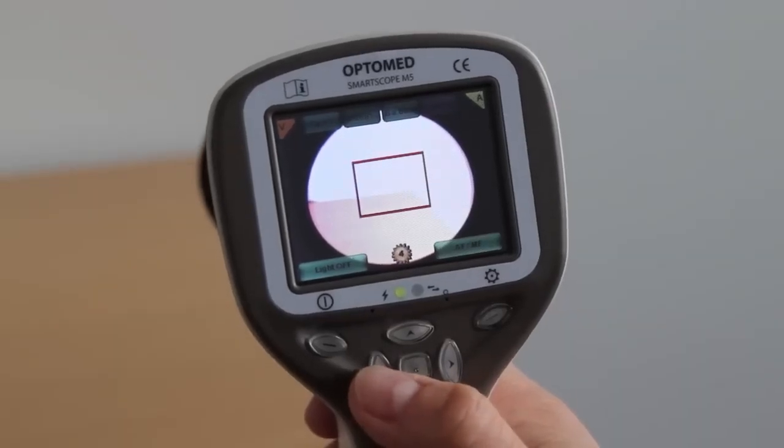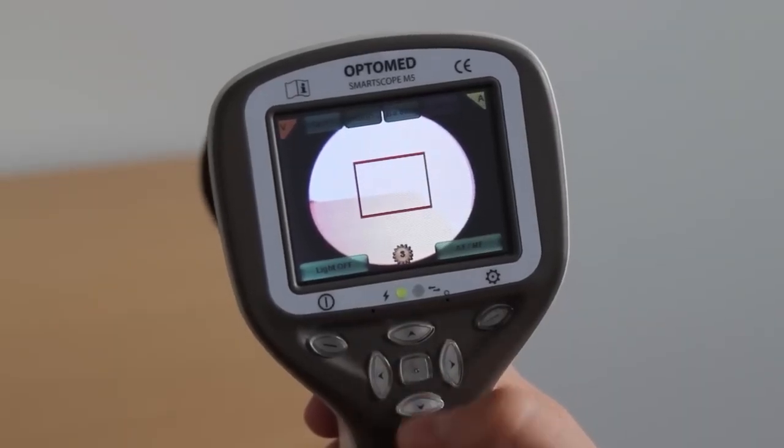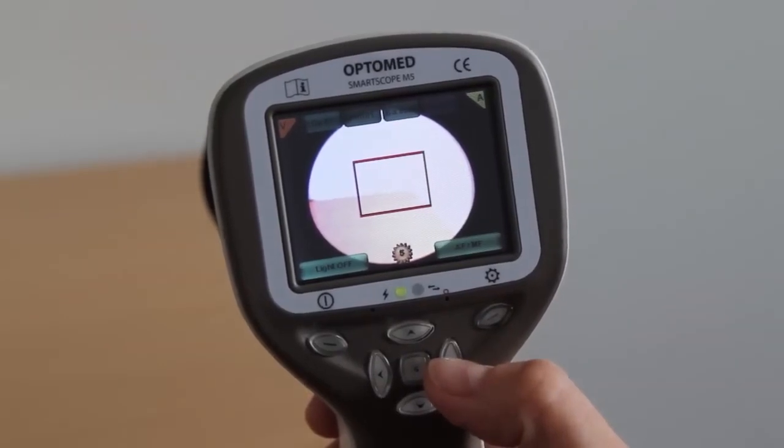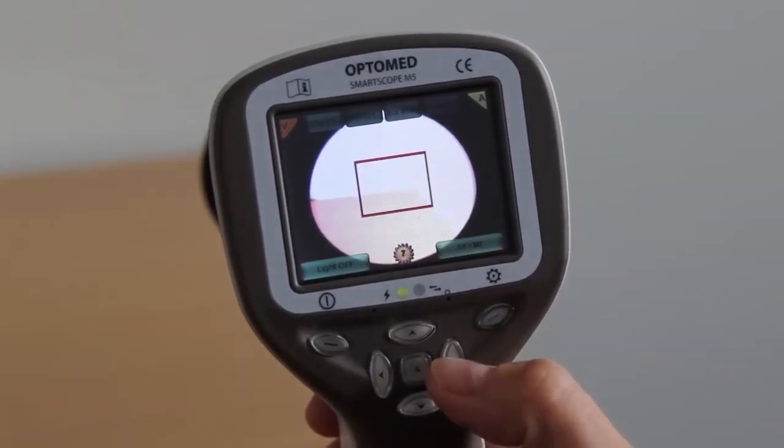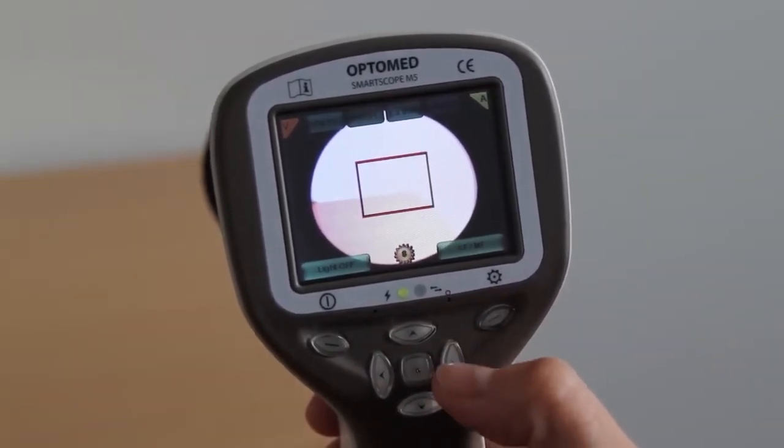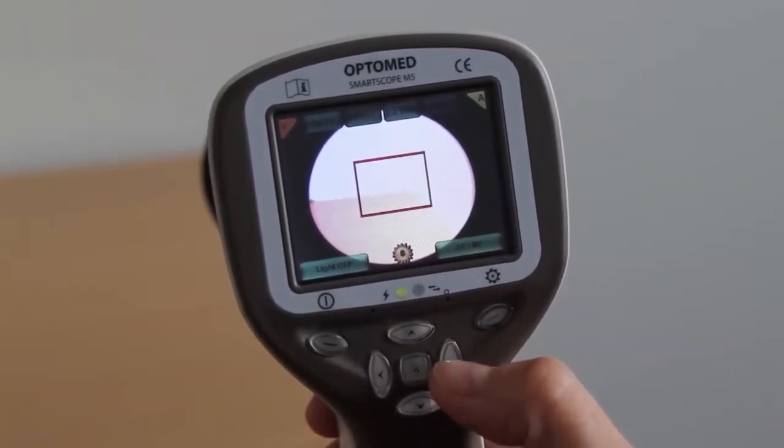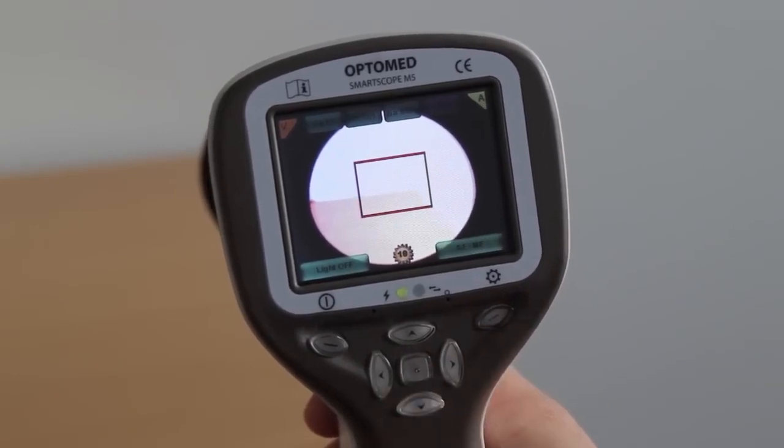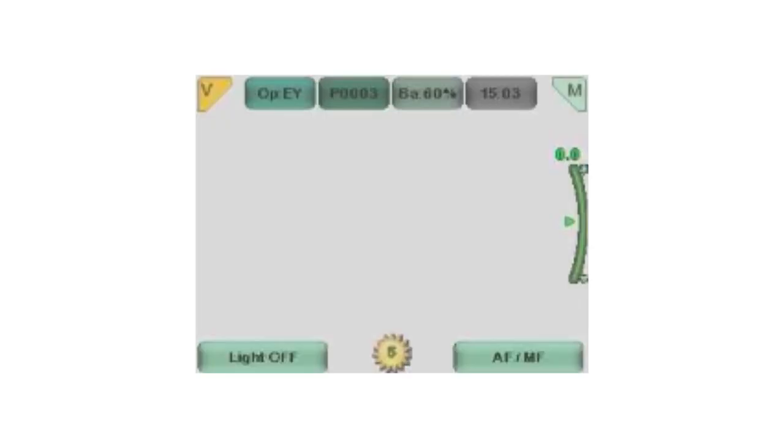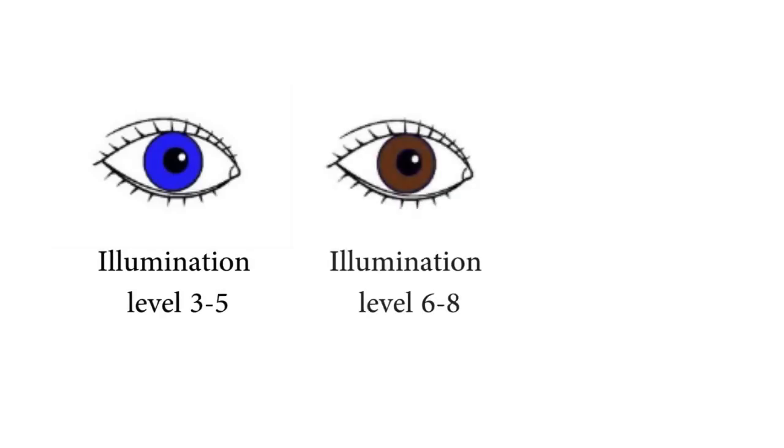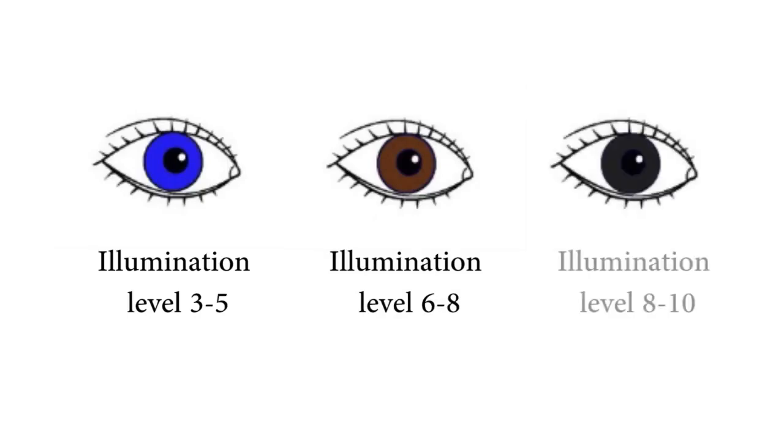Illumination level: The illumination of the white light flash is adjusted by pressing the left and right arrow keys. There are altogether ten brightness levels with a default value of 5. Suitable illumination for a person who has blue eyes is typically in the 3 to 5 range. For brown eyes, 6 to 8 is recommended and for very dark eyes, 8 to 10.